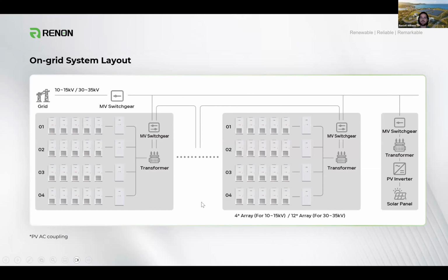This can also tie in external solar as needed, so there's a lot of flexibility. As you can see here, four arrays can get up to that 15 kilovolt range, and 12 can push for higher voltage ranges—true transmission voltage ranges. This is for if you want a utility support setup dropped in a remote location with additional space, where it's easier to do energy production or storage at a lower land cost, while still transmitting it to support full grid level operation.